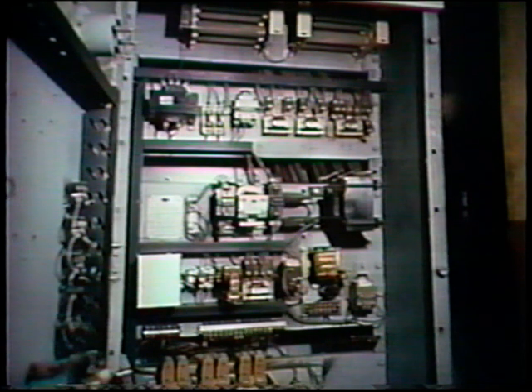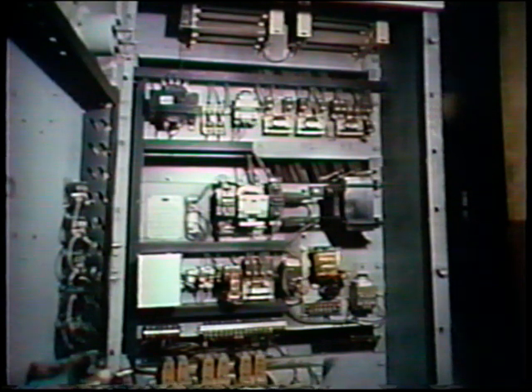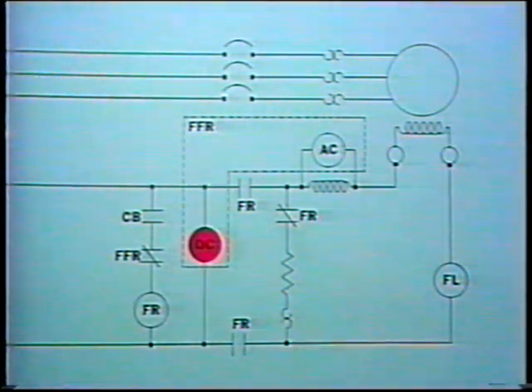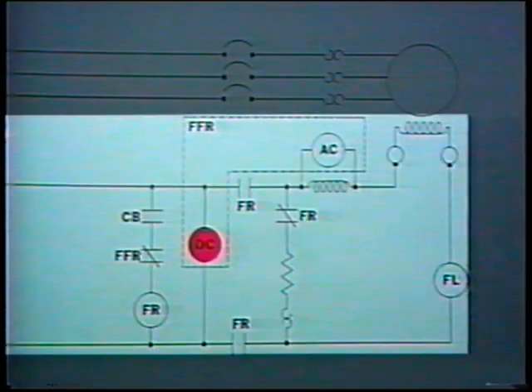At the same time, a magnetic field controller protects a synchronous motor in the event that the rotor windings fail to become energized, or if there is a loss of DC current through the rotor windings during motor operation. A magnetic field controller uses electromagnetic switches to control the opening and closing of the circuit from the DC power supply through the rotor windings. Let's take a look at a simplified synchronous motor controller and see how it operates. The schematic of this controller can be divided into a stator circuit and a rotor circuit.